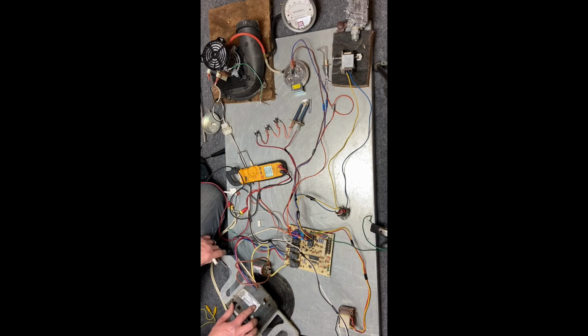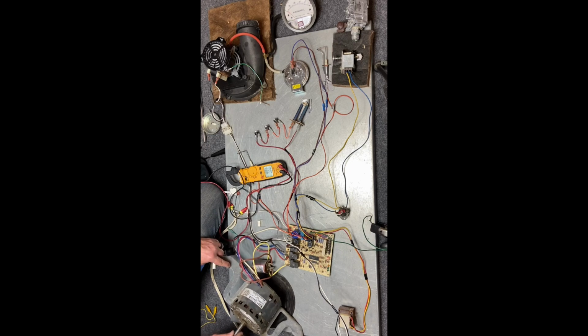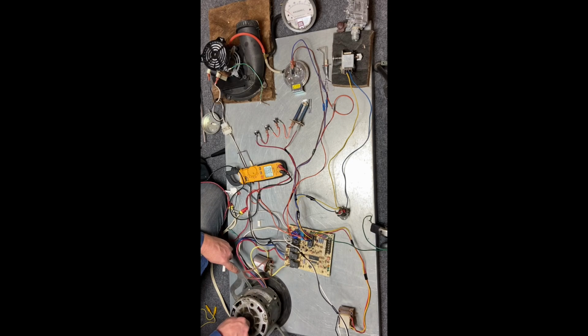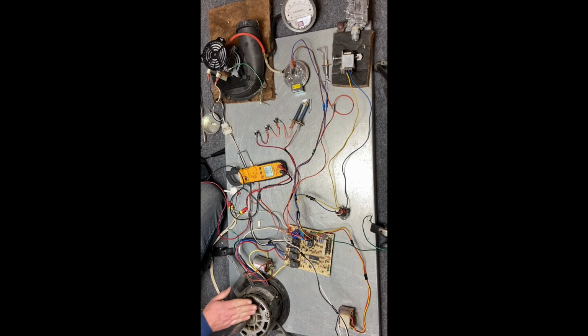If I'm above that number, it doesn't mean the motor's bad. I need to check the airflow. I need to check the evaporator coil. Make sure I'm getting enough air through there. I need to check the blower wheel, several things like that. And if all of that's good, then I start looking at the motor itself. On this one, there's nothing else to really work with. We have a very simple motor. So if I'm overamping on this motor, it's usually going to be the bearings, and we've got to change out that motor. So very simple components to check.